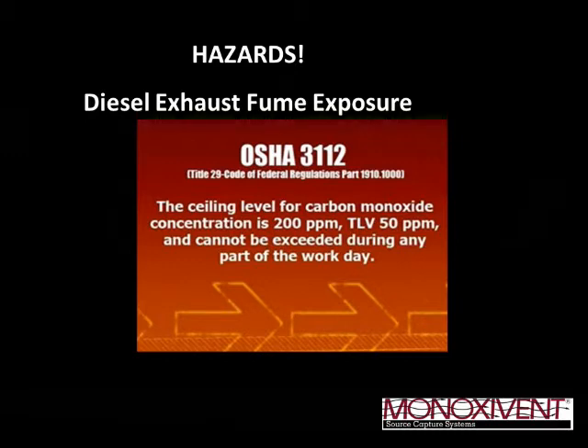The problem I have with that is they're talking about measuring the gases and the exhaust at the ceiling level. As we all know, the majority, certainly not every vehicle, but the majority of vehicles have a below-chassis tailpipe. So the exhaust is being presented at the floor level and measured at the ceiling level. The problem with that is that in between those two levels is our breathing zone, so we're actually filtering the exhaust before it makes its way up to be measured. That's why source capture is the most effective way to prevent that from happening.